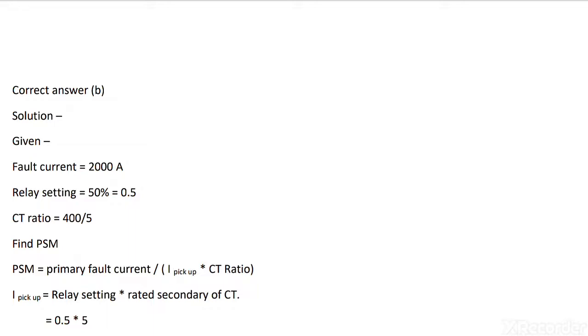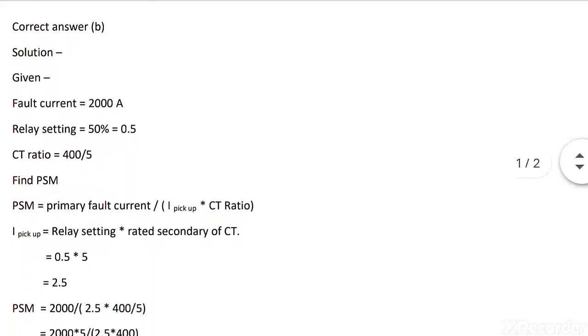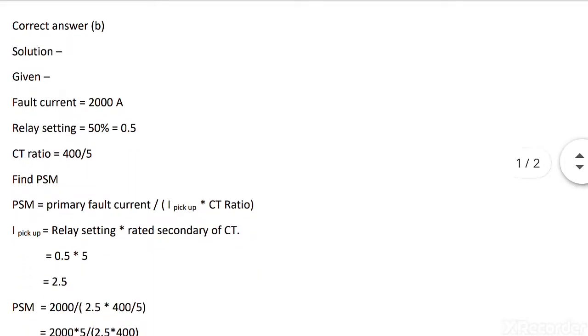Where I pickup is relay setting into rated secondary of CT, equals 0.5 into 5, equals 2.5.